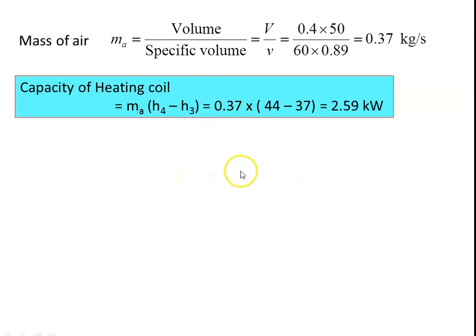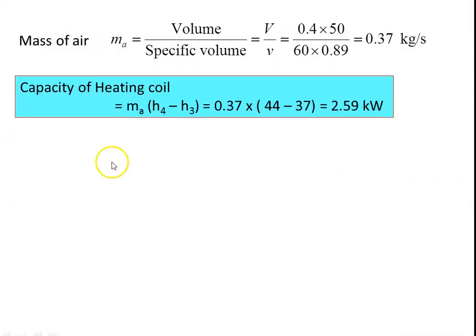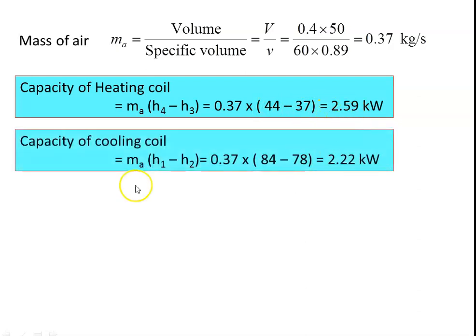Cooling coil capacity uses h1 (initial) to h2 (final), so = ma × (h1 − h2). Capacity of heating coil = ma × (h4 − h3) = 0.37 × (44 − 37) = 2.59 kilowatts. Capacity of cooling coil = ma × (h1 − h2) = 0.37 × (84 − 78) = 2.22 kilowatts.